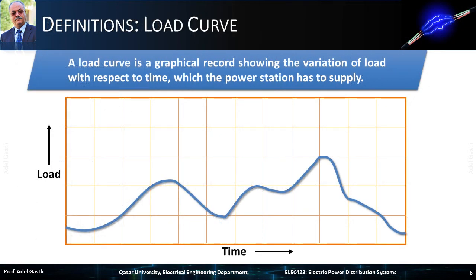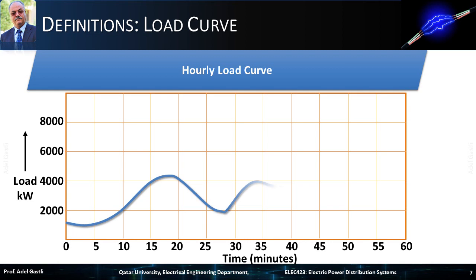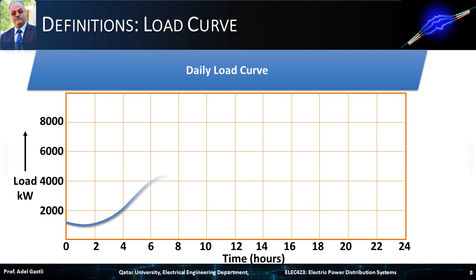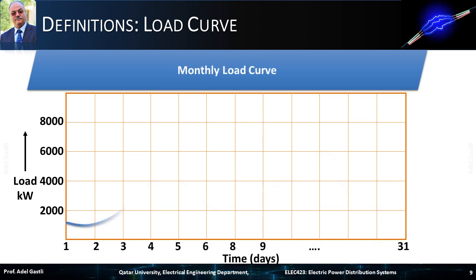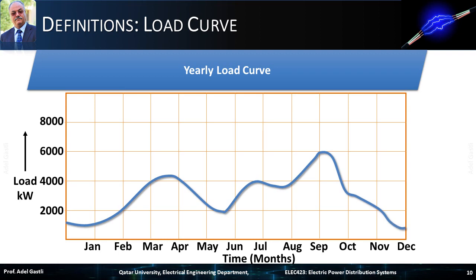A load curve is a graphical record showing the variation of load with respect to time, which the power station has to supply. A curve depicting the load consumed during an hour is called an hourly load curve. A load curve depicting the load consumed in 24 hours is called a daily load curve. If it displays load consumed in one month, it is called a monthly load curve, and if in one year, a yearly load curve.